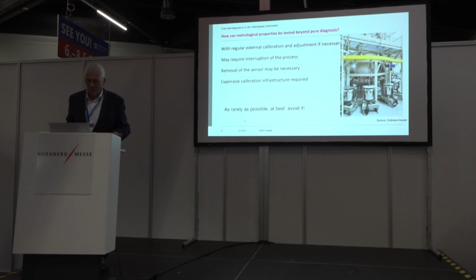The best solution would be self-calibration, where the sensor is able to calibrate itself. Here's an example: for a temperature sensor, we have the standard PT100 element, with a ceramic put on it that changes its crystal structure exactly at a certain temperature. This can be used as an internal fixed point for calibration - when the temperature reaches this fixed point, you have an internal reference and can tell whether your measurement is already okay or needs adjustment. This is already available from my former company and is very successful.